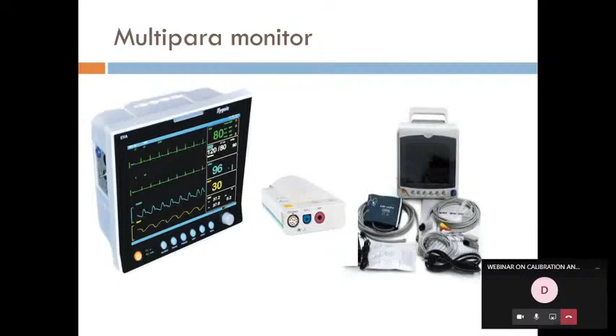Then if you have an issue, the monitor is showing tachy or brady, the doctor will call you and say the monitor is not showing the correct value. Then one option you have is to take the ECG cable and connect it with a simulator. With the help of the simulator, you set a heart rate at 72. The monitor has to show the same 72 value. If it is showing correct, then there is a problem with the patient.